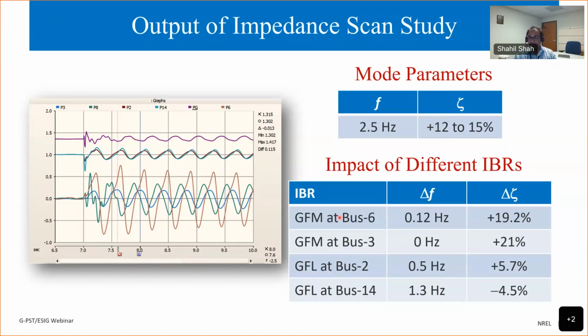And not just that, we can also use this to understand how control tuning might impact the system mode. So for example, if I increase the voltage control bandwidth of any of these grid forming resources, basically make it behave more like an ideal voltage source, its contribution to damping will improve. So the capacity of grid forming resources required in the system for stable operation is also related to the control bandwidths.